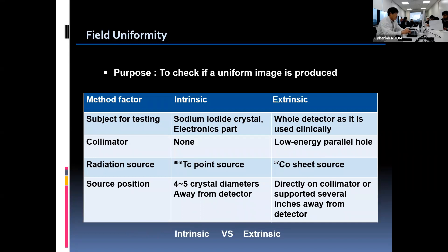Once the energy peaking is verified, we proceed to the uniformity test. Field uniformity is the ability of a scintillation camera to produce a uniform image with a radioactive source that provides a uniform distribution of photons. The test can be done either intrinsically or extrinsically.